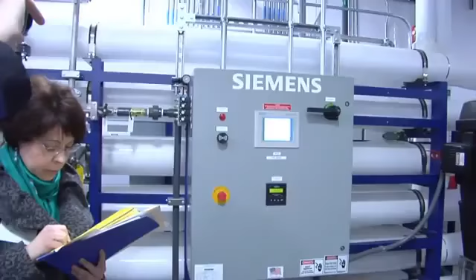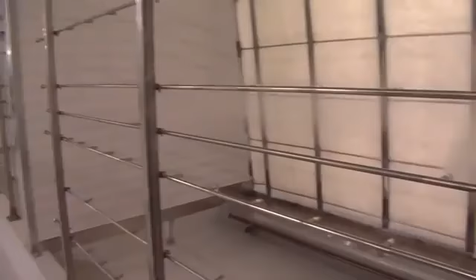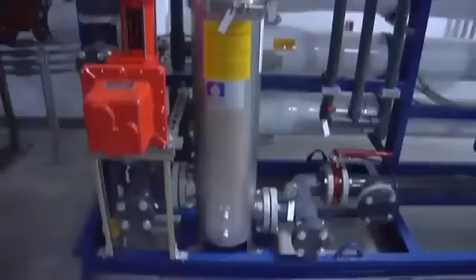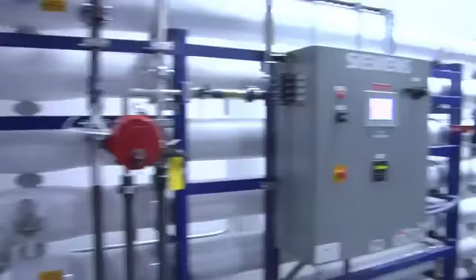One of the important things in an evaporative cooling system is having very pure water. You charge a nozzle and spray water out of it, so you don't want that water to have any minerals or other biological materials in it. You run the water through a reverse osmosis system to get very pure water, then pump it upstairs to the cooling systems, where pumps and nozzles spray it into the air to cool it down. There's also a UV system where ultraviolet light kills any biological material in the water - that's essentially the process to get really pure water.